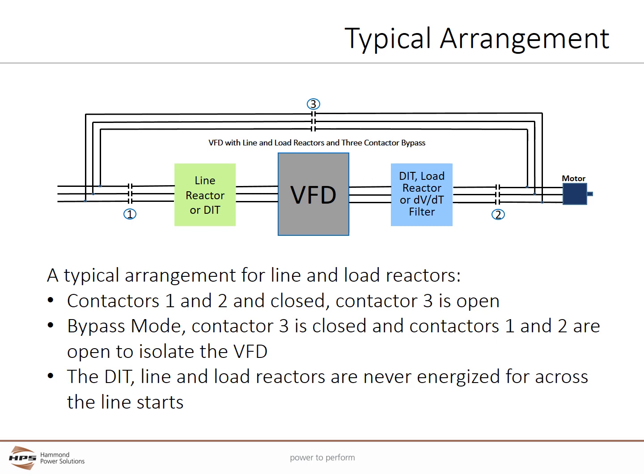When contactors 1 and 2 are closed, contactor 3 is open, and the motor is powered by the VFD with speed control. In bypass mode, contactor 3 is closed and contactors 1 and 2 are open to isolate the VFD, and the motor runs at full speed. The line and load reactors and DITs are never energized for across-the-line starts, since they are designed to work with VFDs and don't encounter the motor inrush currents, which happens with across-the-line start motors.